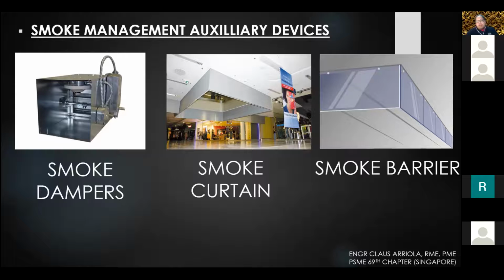There are not all the time that your smoke curtain will be half open, which is what you see in this picture. Based on your smoke management, there are some cases where your smoke curtain must be fully dropped down. Then of course it will affect your design costs if you don't manage it well, because if you buy a very long smoke curtain, it will be very costly.